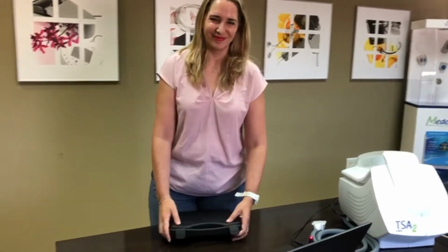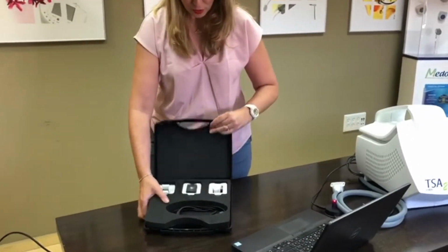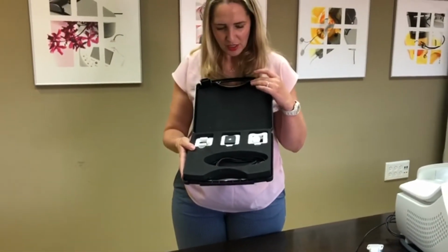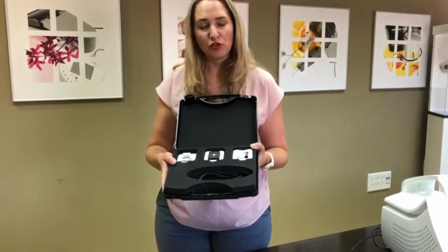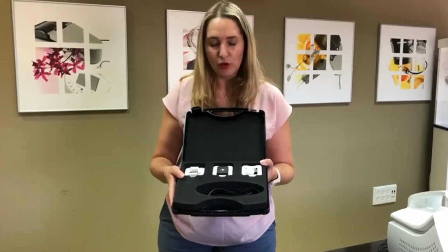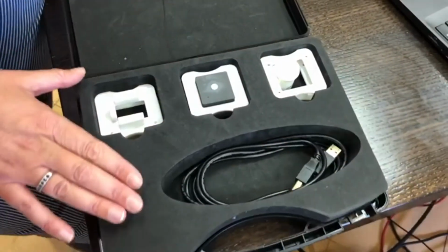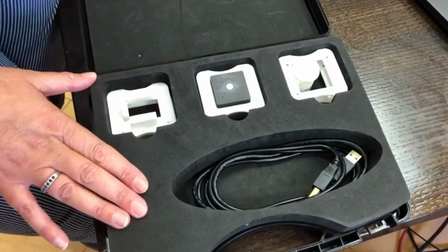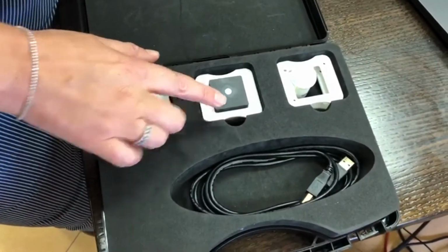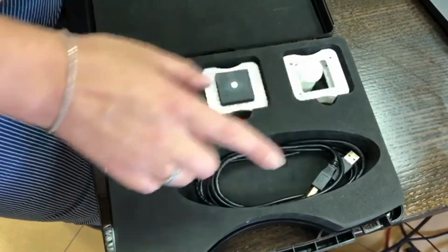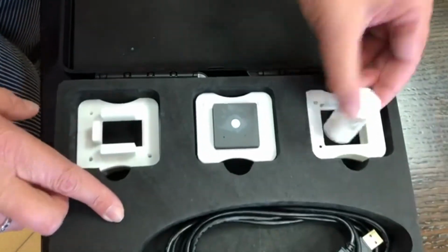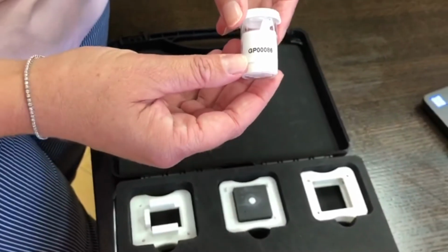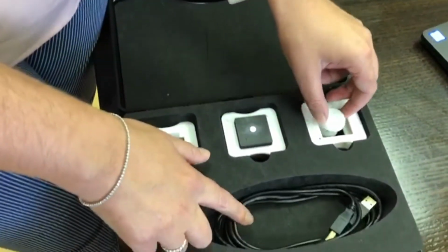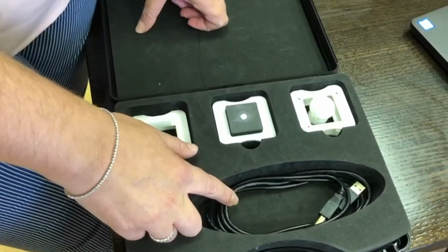New Medoc Cal Kit. The new Medoc Cal Kit comes in this box and it contains several items which I'm going to show you a little bit more close up so you can see it better. So this is the calibration kit from the inside. Over here is the sensor. These are the jigs that will come along with the device that you'll buy. This is the thermal grease, and this is the communication cable that will be connected to your computer.